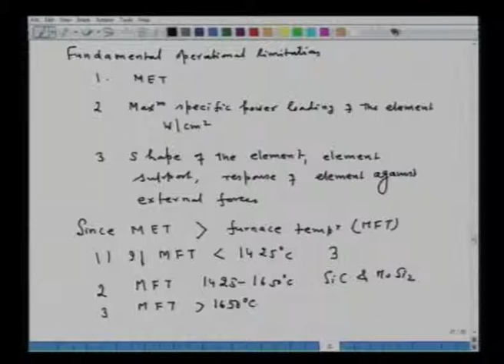So, the choice of course depends upon the maximum furnace temperature required. In addition to this, metallic wires are available both in wire and strip form. Metallic wires can be operated with the line voltage, but silicon carbide and molybdenum disilicide heating elements cannot be operated with line voltage. For that, you require so-called transformers. So, of course, these are some considerations for selection of the heating element. Now, some of the advantages and disadvantages of heating elements. Say for example, I take first metallic elements.